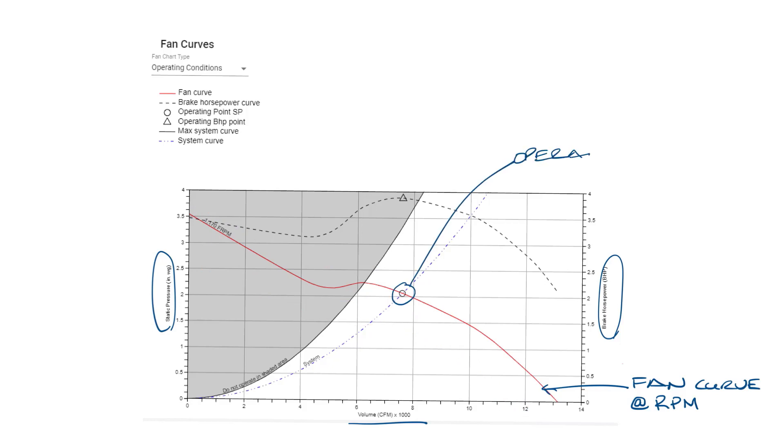This point is our operating point, 7500 CFM at 2 inches. You can see if the pressure was lower, the airflow along the curve would be higher.